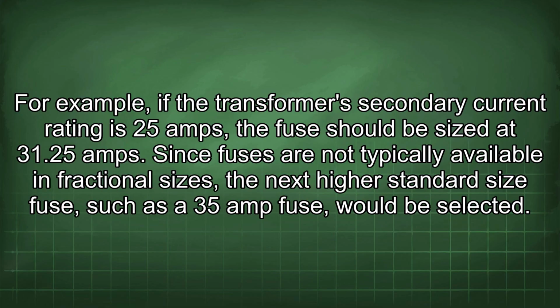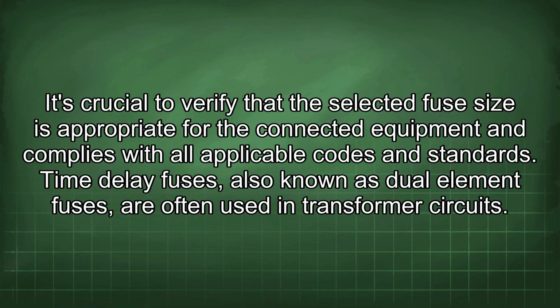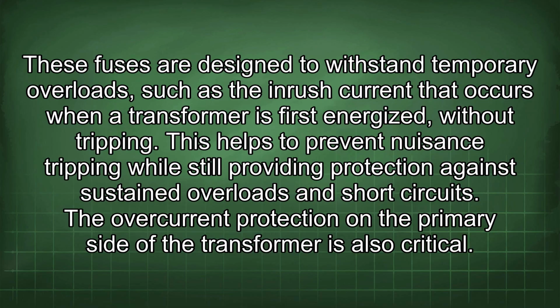Since fuses are not typically available in fractional sizes, the next highest standard size fuse, such as a 35 amp fuse, would be selected. It's crucial to verify that the selected fuse size is appropriate for the connected equipment and complies with all applicable codes and standards. Time delay fuses, also known as dual element fuses, are often used in transformer circuits. These fuses are designed to withstand temporary overloads, such as the inrush current that occurs when a transformer is first energized, without tripping. This helps to prevent nuisance tripping while still providing protection against sustained overloads and short circuits.